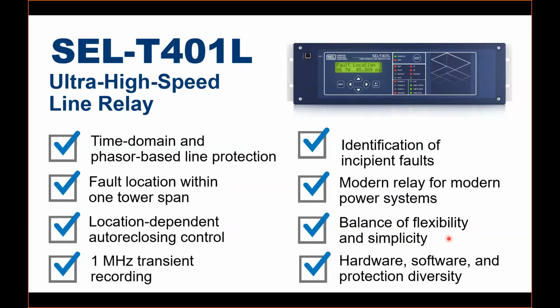And this is the relay which is made from a blank piece of paper, from scratch. So it has nothing to do with the conventional relays or other relays that we are already having for line protection. So you can use it as a set 1 and set 2 because both are based on absolutely independent algorithms and hardware. And simplicity is the core. So we have reduced the complexity in terms of settings, and in terms of logics as well. So the user doesn't need to worry much about the logics or a lot of parameters you need to set.